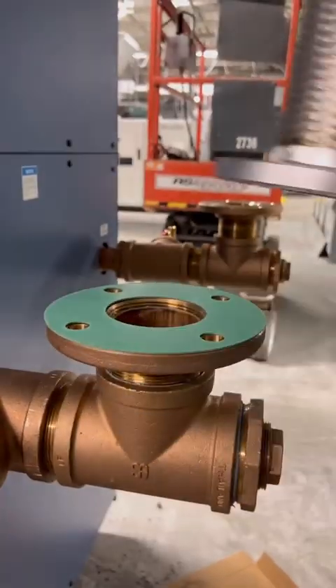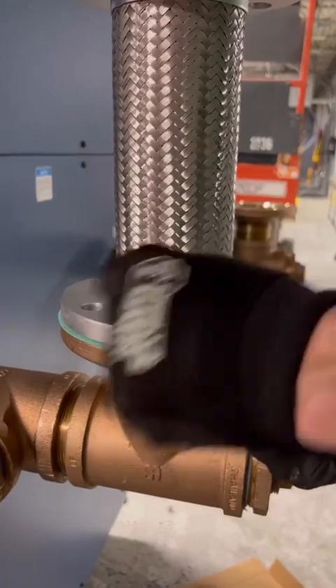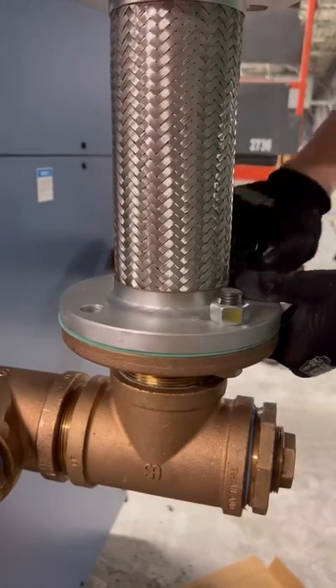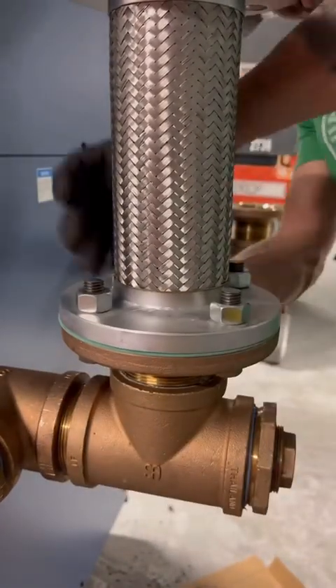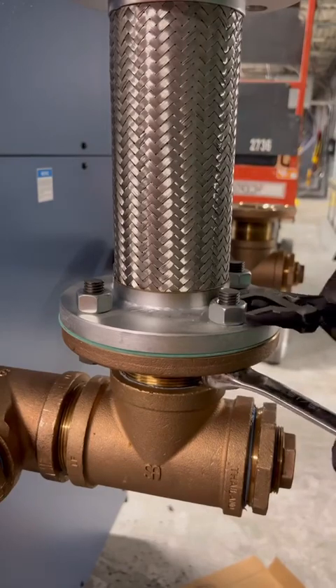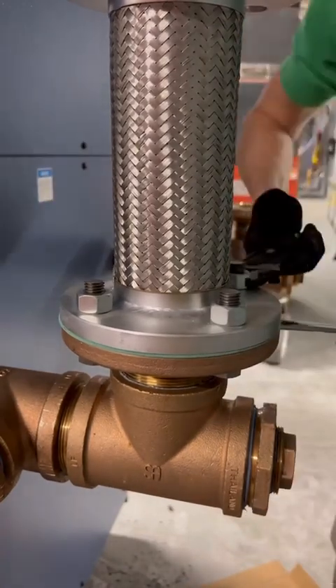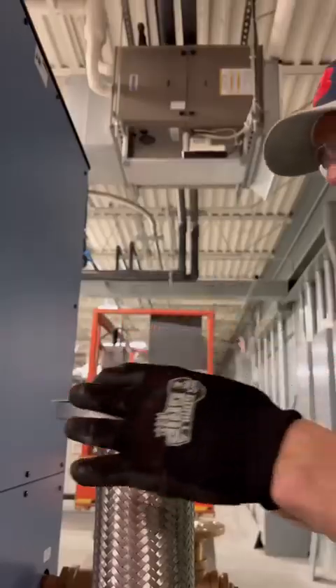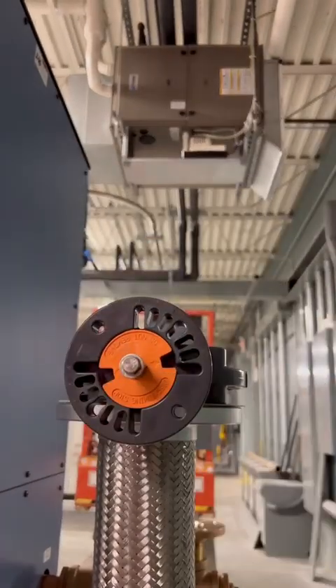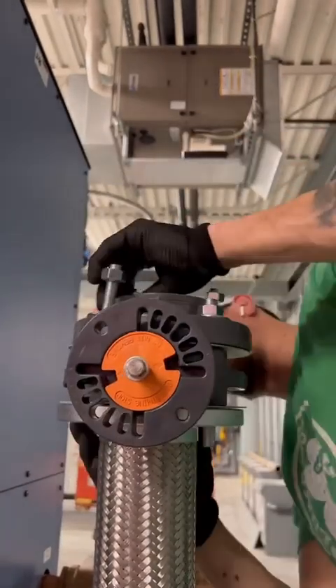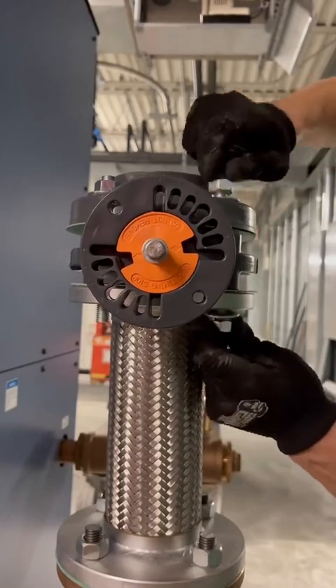So this here is a vibration isolator. So when the unit's running, it's not going to send the vibration through the rest of the piping in the ceiling. And by doing this, I'm able to clip the pipes to the unistrut above. There's the butterfly valve, and we're transitioning over to Schedule 80 PVC.